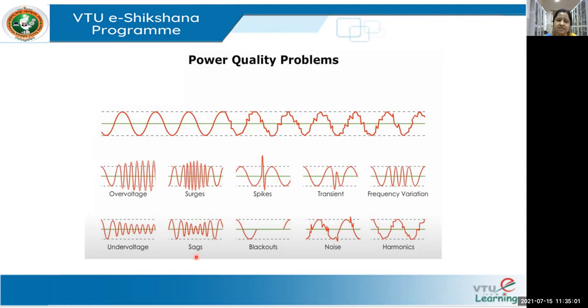A sag — or dip — in the voltage means your waveform is not able to maintain that one per unit nominal value. Between 10% and 90% dip in voltage, as per the IEEE 1159 standard, is defined as a voltage sag. A blackout, or interruption, means the system has come to a halt — a serious issue in power quality.